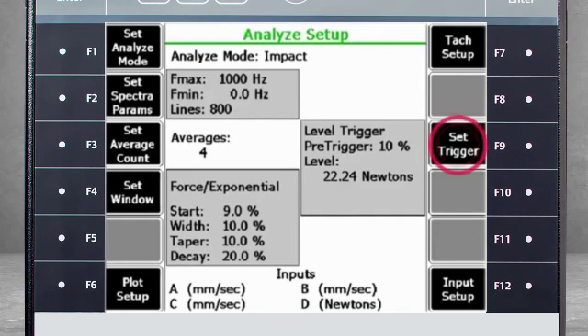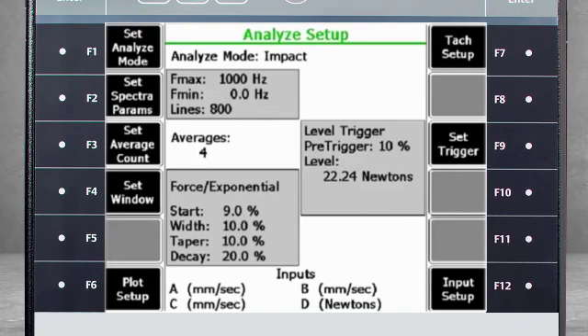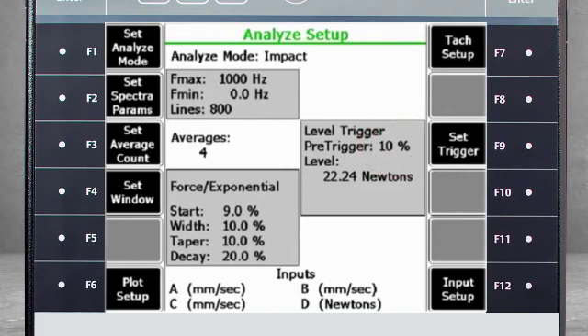F9 Set Trigger is important because it keeps the data collection in wait mode until it feels an impact. When an impact is felt by the analyzer, it will trigger data collection. Note the 10% pre-trigger. That means that the measurement displayed will include 10% of the measured time leading up to the impact.